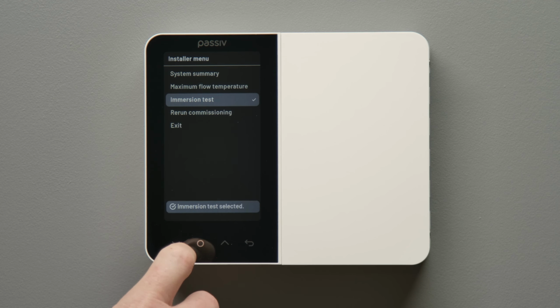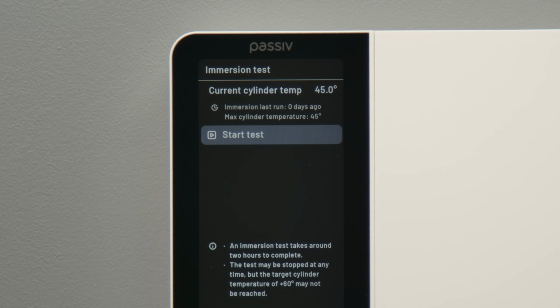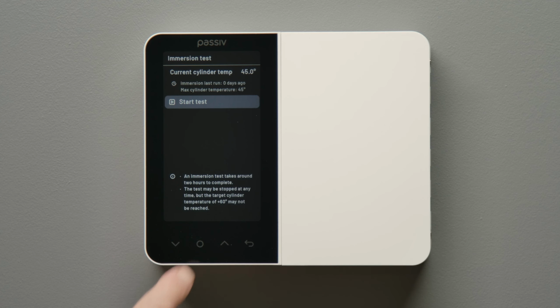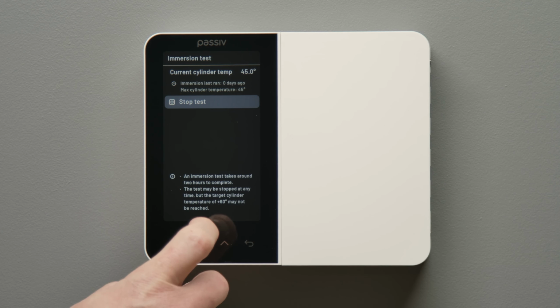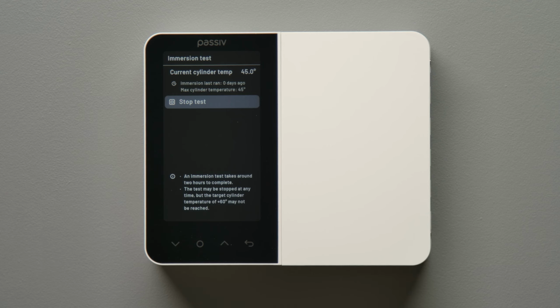This screen shows the current tank temperature, details of when the last immersion test was run, and the maximum cylinder temperature achieved during the last test. You can start a new test by selecting Start Test. This will override the data from the last run test displayed on this screen.